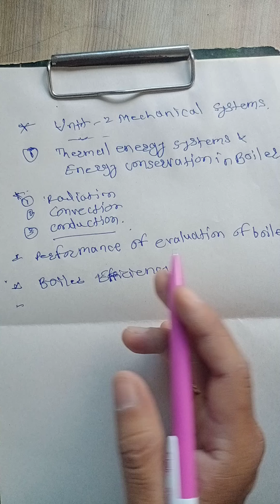What is direct method? This is also known as input output method due to the fact that it needs only the useful output and the heat input for evaluating the efficiency. The efficiency evaluated by this direct method is boiler efficiency. Efficiency is equal to heat output divided by heat input, very simple formula, into 100. The parameters to be monitored for the calculation of boiler efficiency by direct method: one is quantity of steam generated per hour in kg per hour, then quantity of fuel used per hour in kg per hour, the working pressure and superheat temperature, if any, temperature of feed water, type of fuel and gross calorific value of fuel. Boiler efficiency is equal to Q (Hg minus Hf) divided by Q into GCV into 100, where Hg is the enthalpy of steam in kilocalorie per kg of steam, and Hf is the enthalpy of feed water in kilocalorie per kg of water, right?